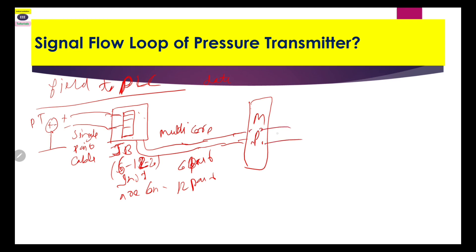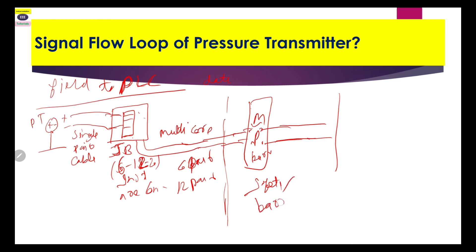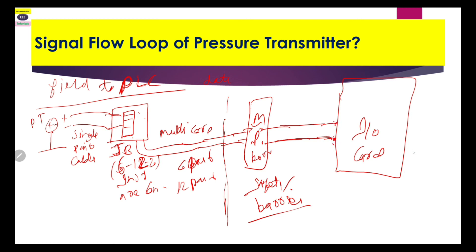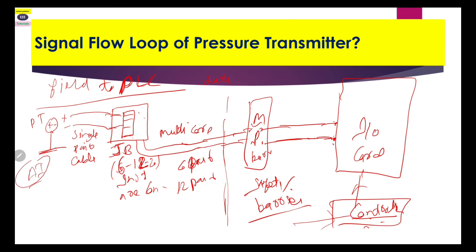At the marshalling panel, some terminal arrangement is there, and then it goes to the PLC I/O card. If there is a hazardous area present in your oil and gas sector, safety barriers are also used. The I/O card has two wires connected, and then the I/O card communicates through your controller. The programmer writes your controller logic where this analog input (AI) signal can be used for interlocks or some other purpose.